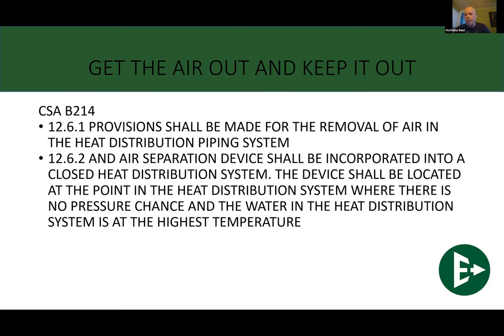So with that being built in, and it even tells you where they want it to go, these are systems now that we are seeing a lot more of. Now, some of these air separators are better than others. You have your standard air scoop. Taco and Amtrol made them for years, where it's basically just a big cast iron log with a couple of scoops on the inside that, as the water went through, saw a bit of a pressure drop, the air rose to the top and got scooped out and put out the air vent on the top.